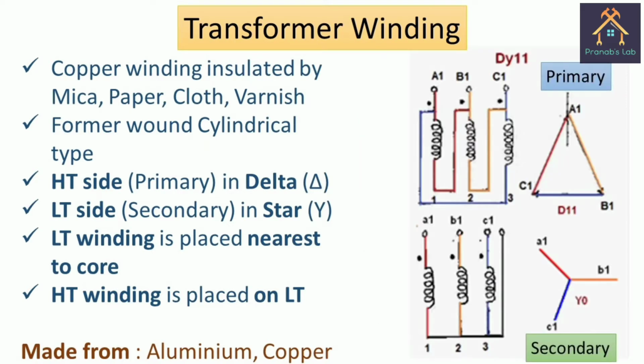The high tension winding is connected in delta having only 3-phase terminals, and the low tension winding is connected in star having 3-phase with neutral terminals. The connection is called Dy11. I will discuss the vector grouping in another video.